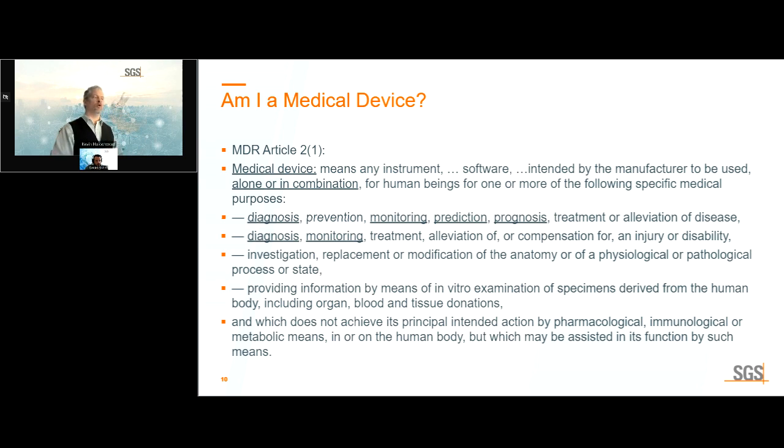Measurement is the same old standard that it was under MDD, if you've been doing this for a while, where the device either is directly measuring an anatomical parameter of some fashion, or it's displaying an energy delivery or a substance delivery. It displays it in SI units, and there is an implied accuracy, meaning if what's on the screen is untrue, there are medical consequences.